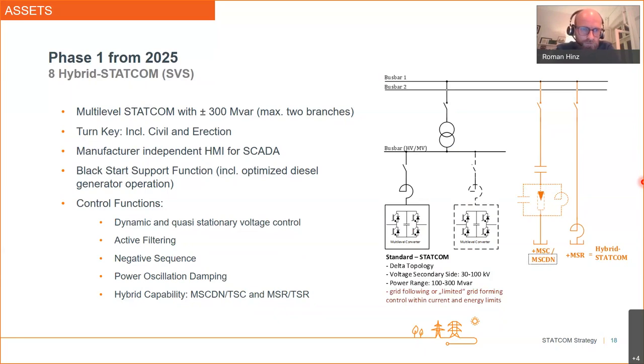We start to tender for these 8 STATCOMs. So it will be a normal multi-level STATCOM with 300 MVA up to 2 branches. And with 2 branches, I mean it could be, for example, 2 converters. Not every manufacturer can supply, for example, one 300 MVA converter STATCOM with 1 converter. So we also give the option to install 2 150 MVA STATCOMs and converters and put them in parallel. So there are several options.